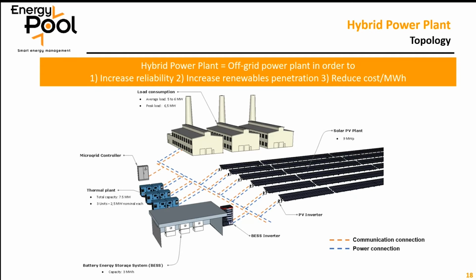Okay, so we move to the third part of this webinar, with the presentation of the hybrid power plant. Hybrid power plant has a lot of definitions. What do we call a hybrid power plant at Energy Pool? It is a factory that decides to disconnect from the main grid and is supplied by distributed energy resources, in order to increase reliability, to increase the renewable penetration, and to reduce the cost of the megawatt hour. In this presentation, we will take the example of a factory with an average load of 5 to 6 megawatts that will be supplied by a solar PV plant of 9 megawatt peak, a battery energy storage system of 3 megawatt hour, and a thermal plant of 7.5 megawatt with 3 gensets of 2.5 megawatt. And of course, we will have microgrid controllers that will monitor and control all the different assets. Please, Jean-Pierre.